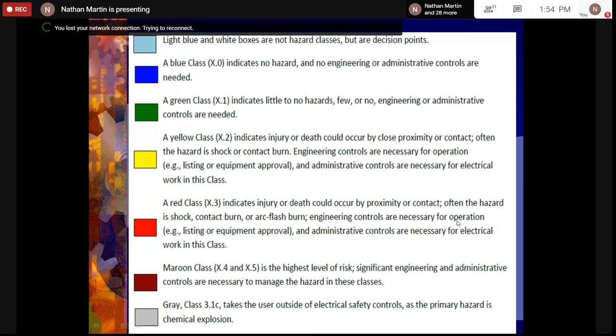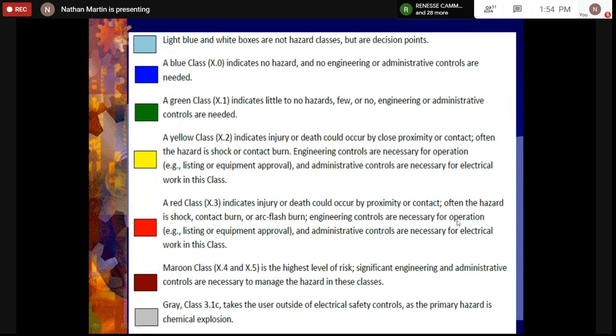And maroon is, as I said, just an intensification of red. So both engineering and administrative control are significantly needed. And gray takes the user outside electrical safety control as a primary hazard, which is chemical explosion. So gray is really beyond electrical means, and you need chemical protection against chemical explosion, like for instance oil-filled transformers and so forth, these have both a chemical aspect and an electrical aspect to them.